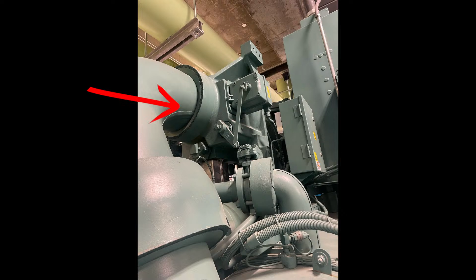What is important, probably the most important thing with installing one of these, is that we get the vanes... Now I'm just going to use the VGD here as the example. We need to make sure the vanes are fully closed at a bare minimum, meaning that the actuator has been driven to the full closed position, which should be a 90-degree actuator. So we're in a fully closed position, and our end switch for closed has been triggered. We're sending that output out, and then we're going to pivot our armature to where we can move to a fully closed position on the armature. So for this actuator down here, that should be a full swing clockwise, if memory serves.